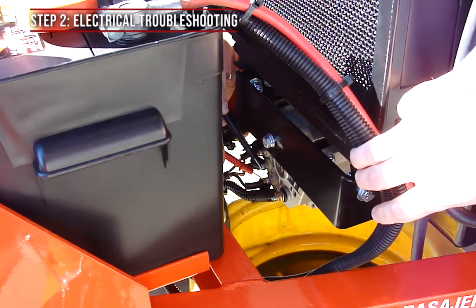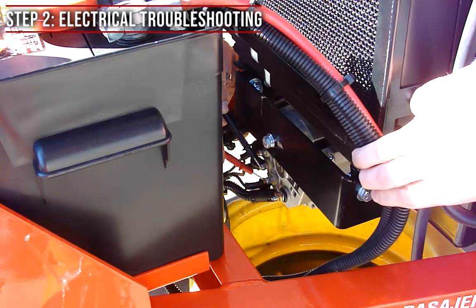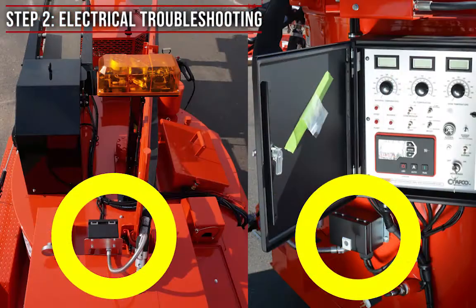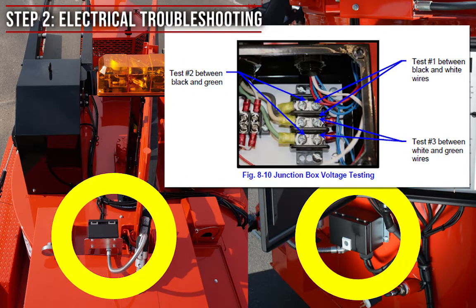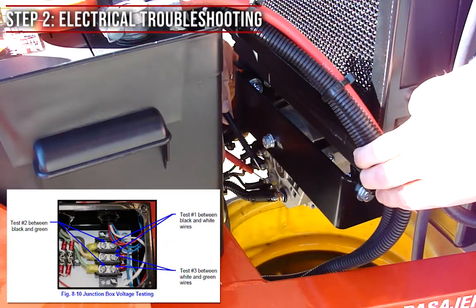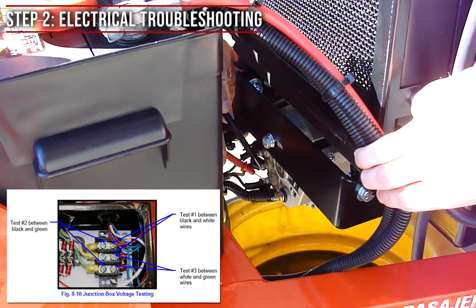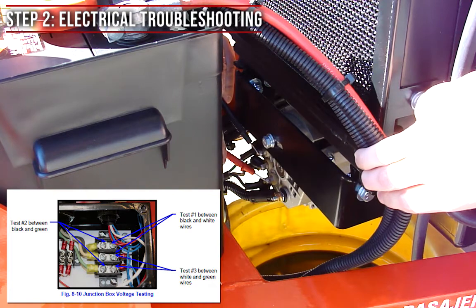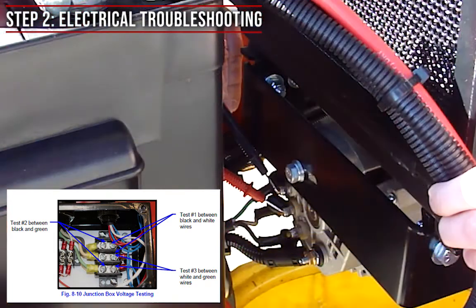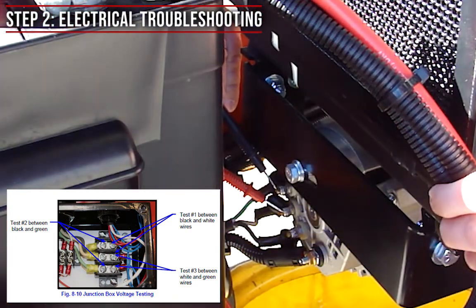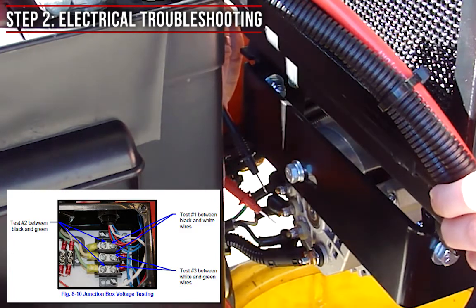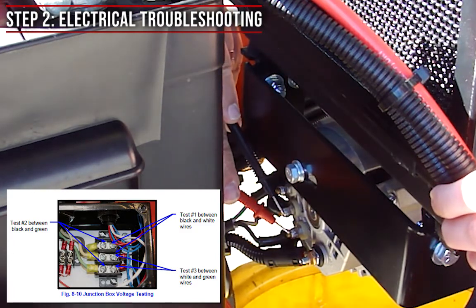Step 2 of electrical troubleshooting is to check for 24 volts at the generator. You will need to check 3 sets of leads, checking between black and white, then checking between black and green, and then checking between green and white. There should be 24 volts between each. This test can also be conducted on the wires inside of the junction box, and again, testing those same combinations of wires. If yes, you get 24 volts between all 3 sets of wires, go on to step 2A.